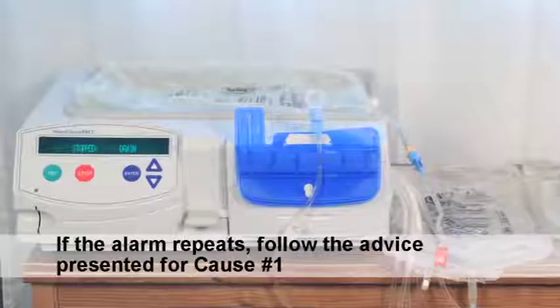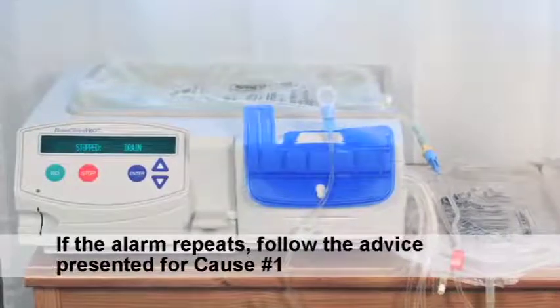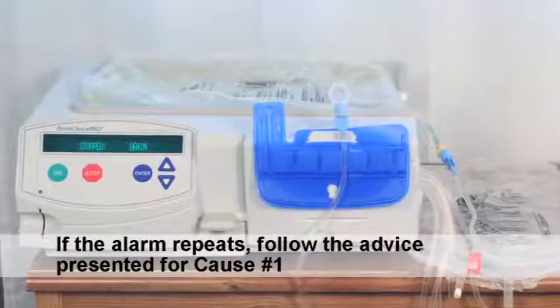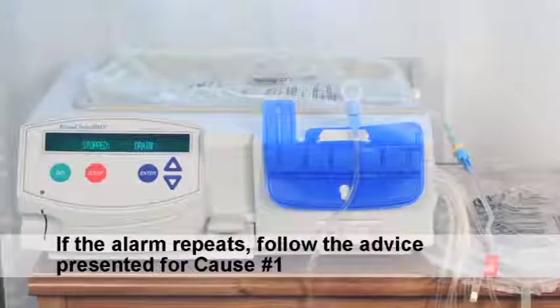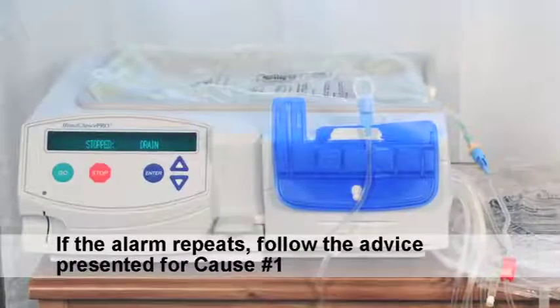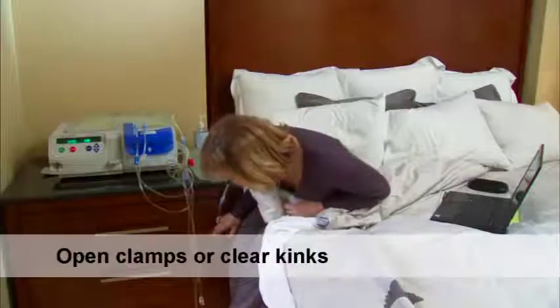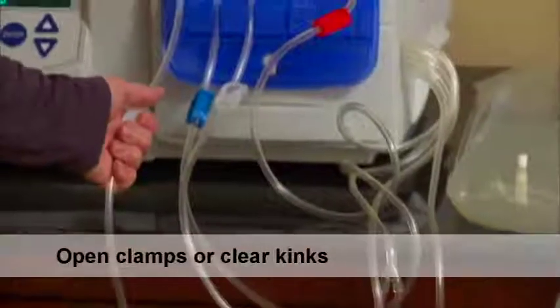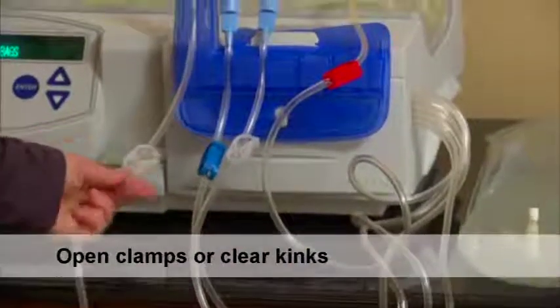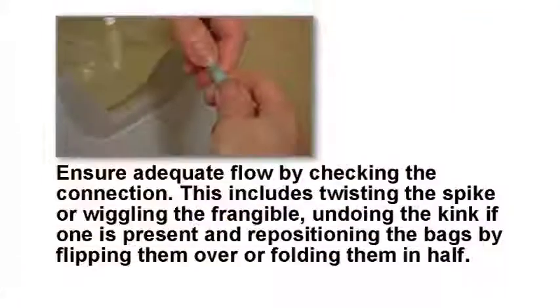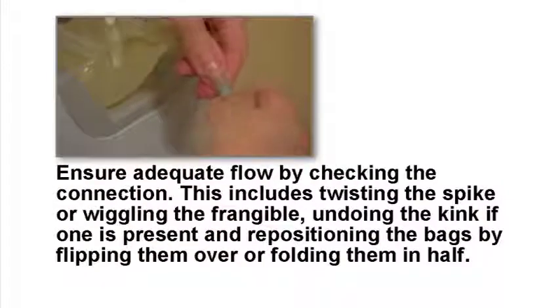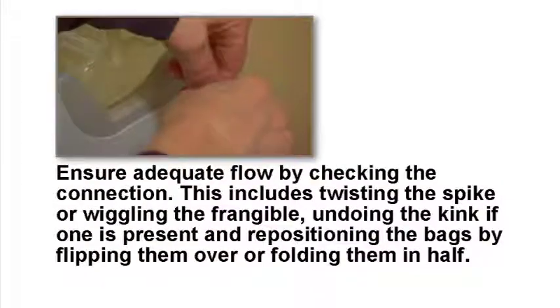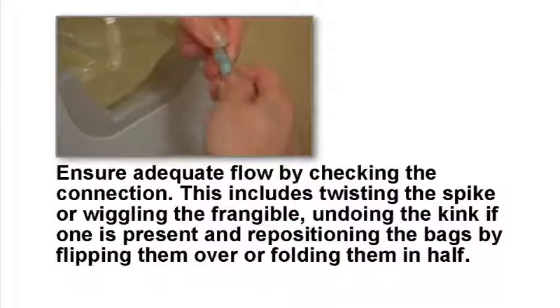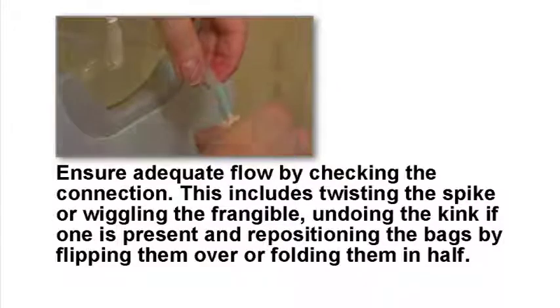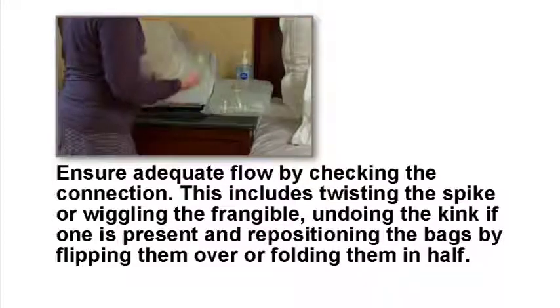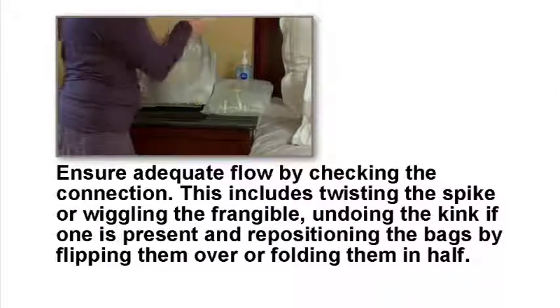If the alarm repeats, follow the advice presented for cause number 1 regarding making sure additional solution is available for priming all necessary lines. Correct the issue found. Open clamps or clear kinks. Ensure adequate flow by checking the connection. This includes twisting the spike or wiggling the frangible, undoing the kink if one is present, and repositioning the bags by flipping them over or folding them in half.